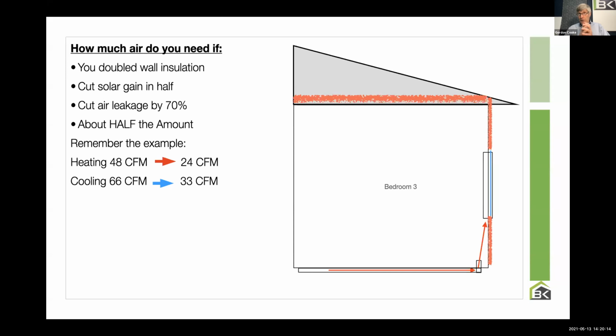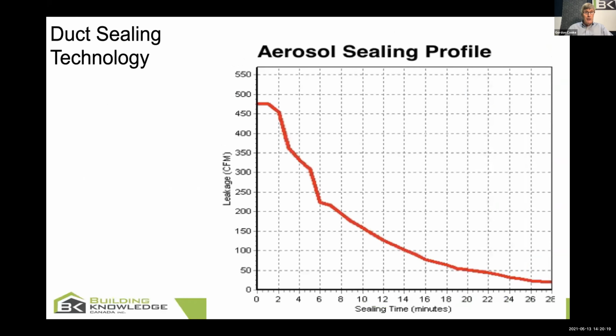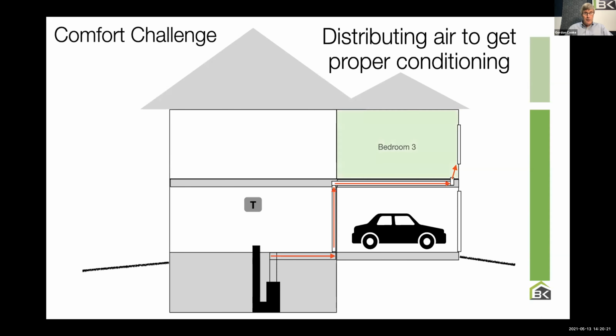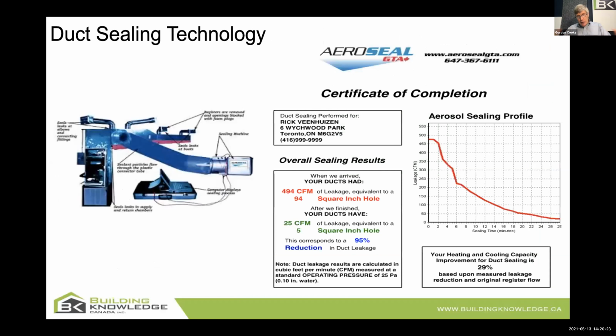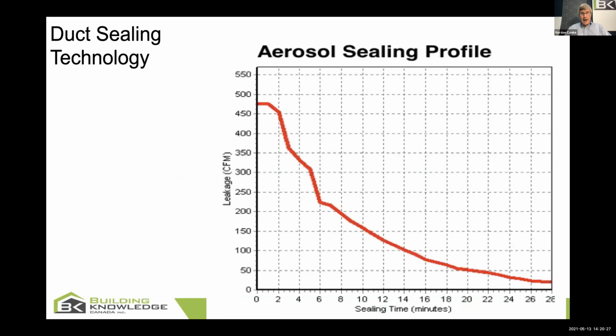So one, fix your duct leakage. Sorry, my apologies, Steph. Somehow a slide flipped on me. I'll go to this one. Let me do this Aeroseal. Notice the graph on the right-hand side. I'll highlight that. There's what happened to duct leakage over 28 minutes. It went from about 20% down to about 2% duct leakage.